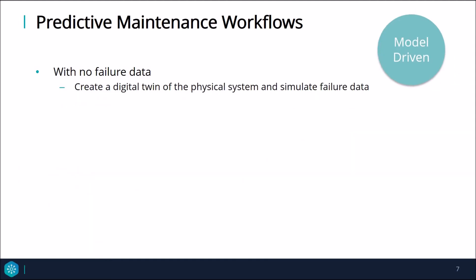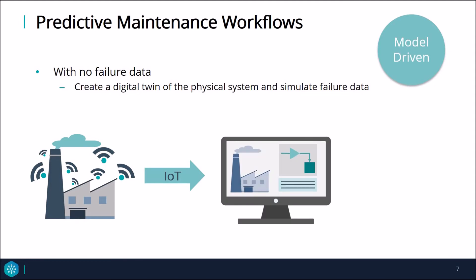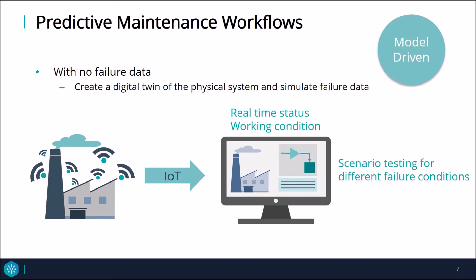When we have no failure data, we can also choose to use a model-driven workflow. For this, we have a physical plant with sensors linked to the Internet of Things. The sensor data is stored in a database or historian. From the sensor information, we can build a digital model which simulates the physical plant using methods like system identification. Using a digital twin in conjunction with the physical plant gives us a good idea of how accurate our model is, to the point where we can use the digital twin to view the real-time status and current working condition of the plant. Once we have a digital model, we can simulate failure events and gather the data generated for different scenarios, which will be used for training a predictive model.